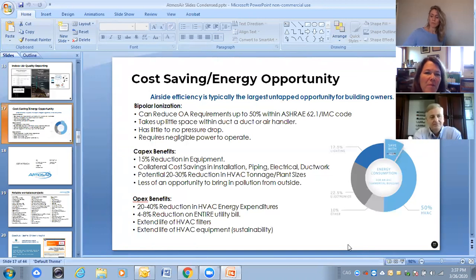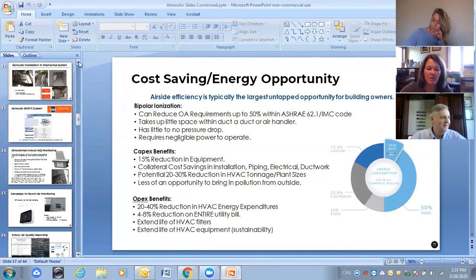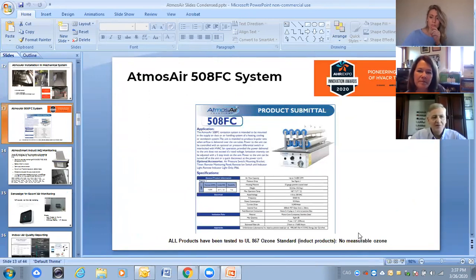What about maintenance of a system like this? Does the equipment need to be replaced or tuned up? That's a great question. We knew early on that a lot of building operators, and even homeowners, don't maintain things the way they should. So we designed the system, with the help of good engineers, so that the only maintenance required is every 2 years: the bipolar ion tube needs to be replaced, almost like replacing a light bulb, you just take it out and put a fresh one in. Sensors similarly need a recalibration or refresh every 2 years. That's the only maintenance you'll ever need, and otherwise it requires no other human intervention.